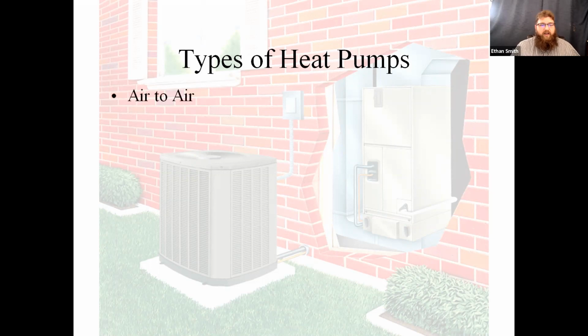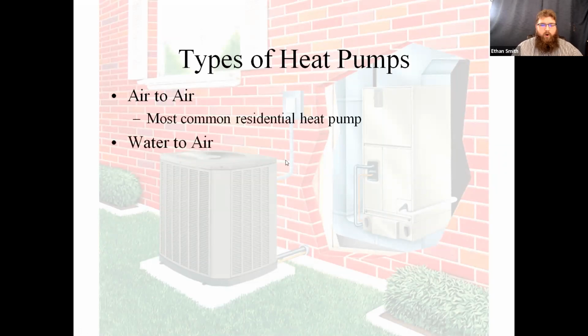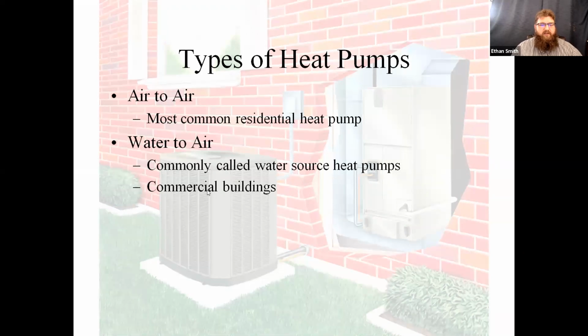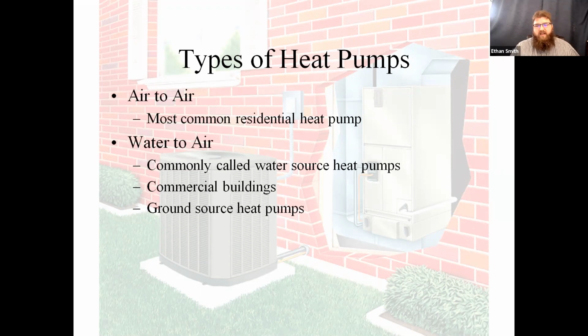Most common that we see are air-to-air heat pumps, which means we have an air source heat pump outside, and we have an air-to-air unit inside. We also have water-to-air style heat pumps. We see this a lot with water source heat pumps or geothermal units. We also have commercial buildings that have cooling towers and things of that nature, where we use a water source on the outdoor section, what would be considered the outdoor section, and we use an air-to-air coil on the inside. We also see this a lot with ground source heat pumps, where instead of a condenser outside, you'll have a compressor and water pump on the inside. It pumps water through piping in the ground and pulls heat out of the ground in the winter and puts heat into the ground during the summer.